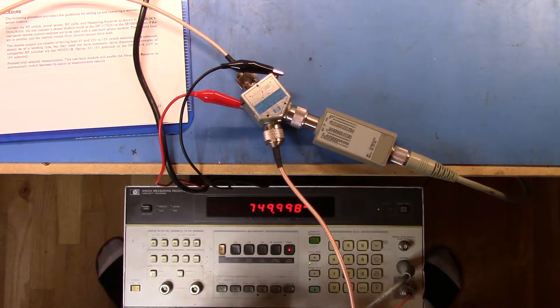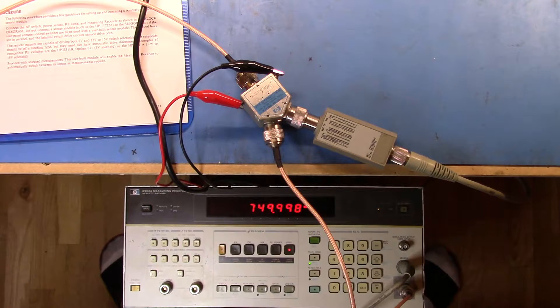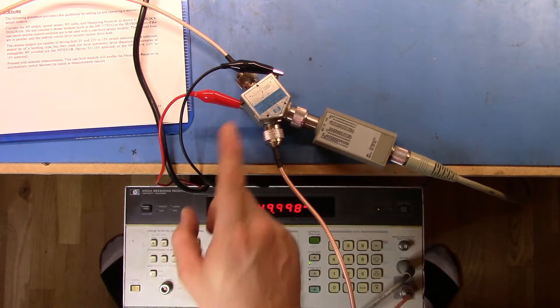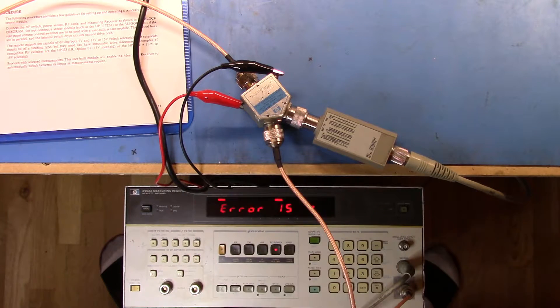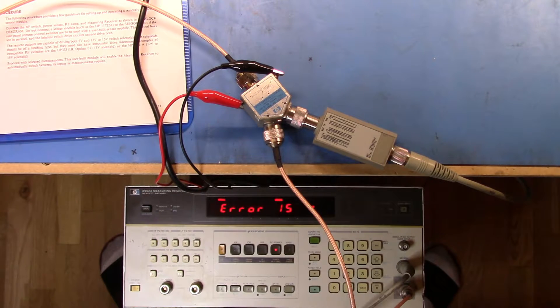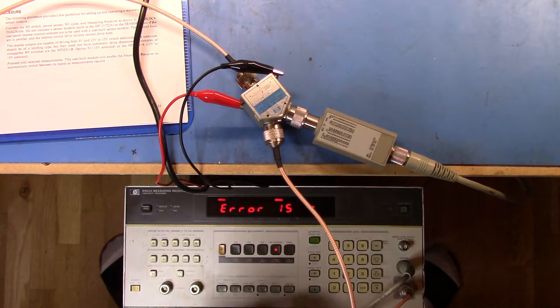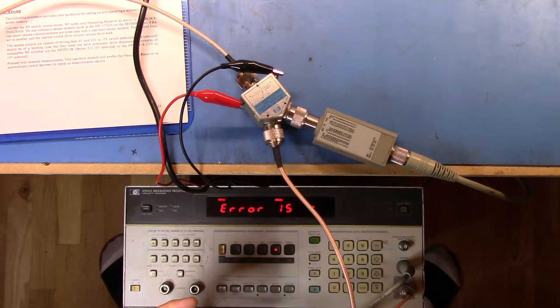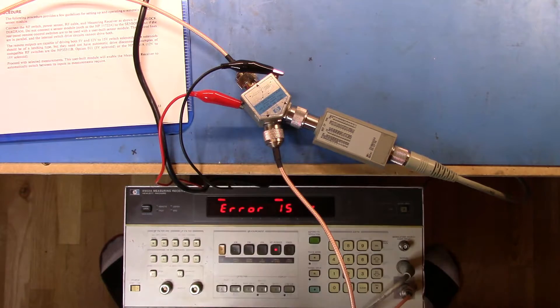So we'll keep coming back and trying that, but let's just clear that and you can see the frequency there and it'll eventually come good and hit 750 once that warms up. So now if I hit RF power you should hear a clunk and I'm getting error 15 because that's telling me that we haven't set any of the calibration factors that would enable the system to calibrate. So let me go do that and then I'll be right back.